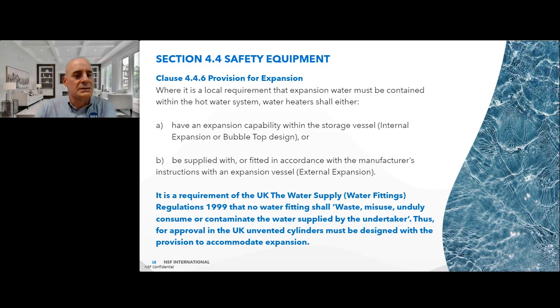Clause 446 is the provision for expansion. So where it is a local requirement that expanded water must be contained within the hot water system, water heaters shall either have an expansion capability within the storage vessel, or internal expansion, or bubble top designs as they're also known, or be supplied with or fitted in accordance with the manufacturer's instructions with an expansion vessel, and these are normally known then as external expansion units.